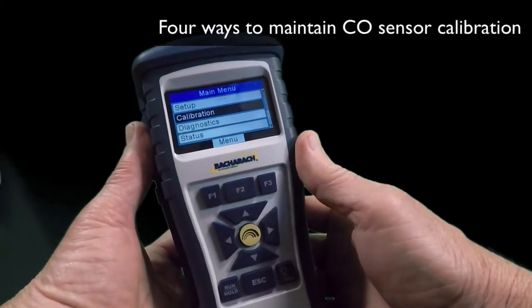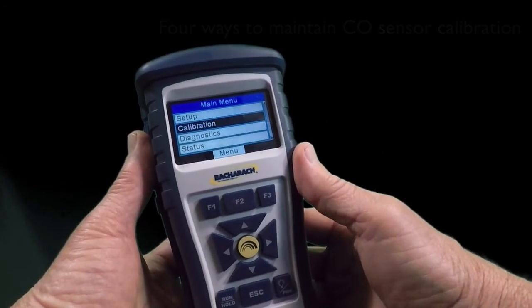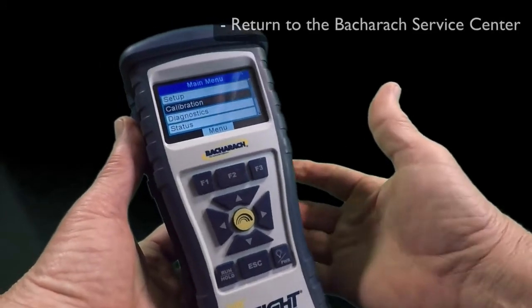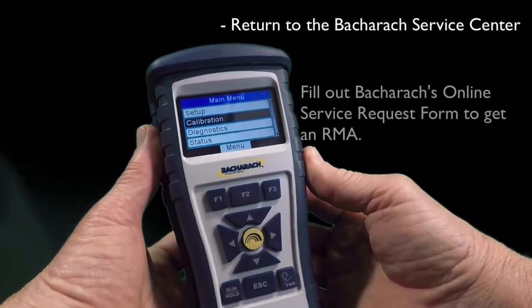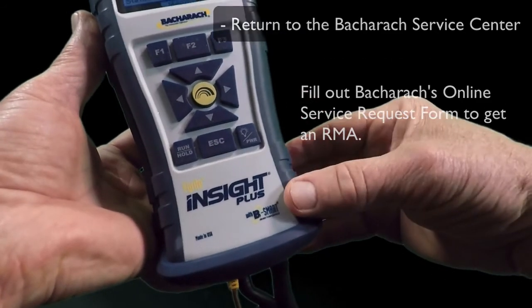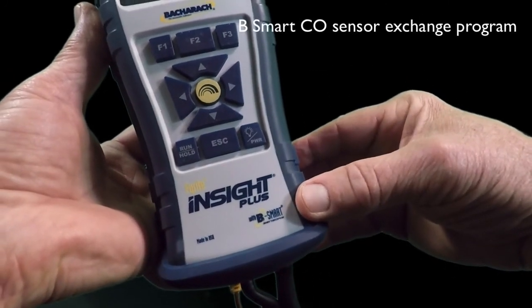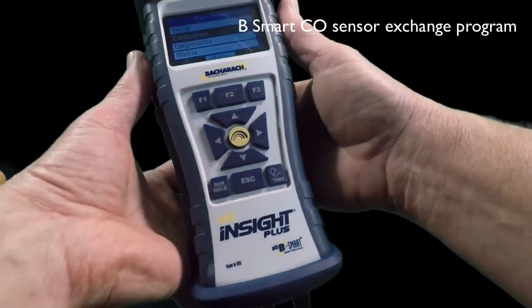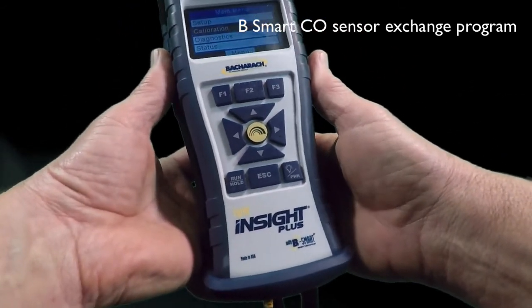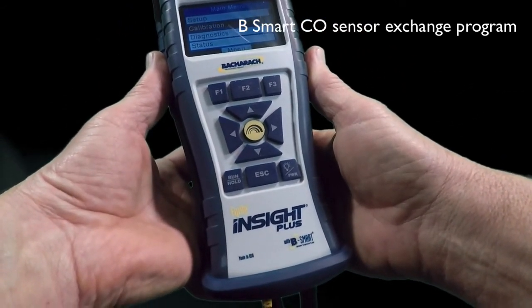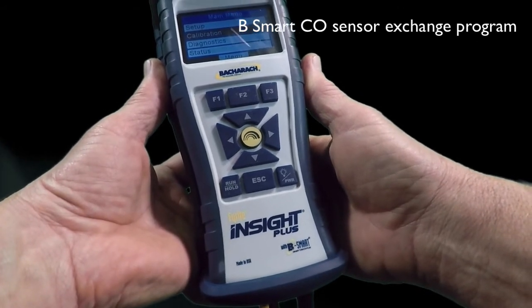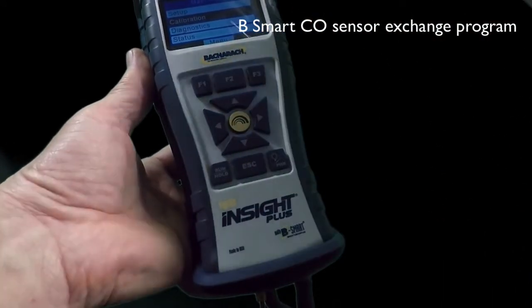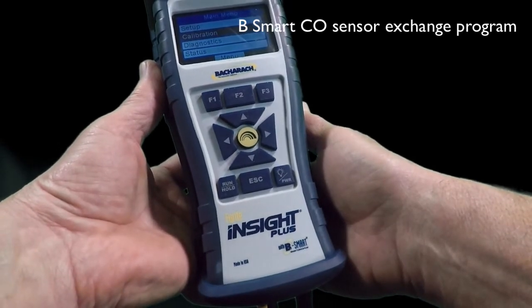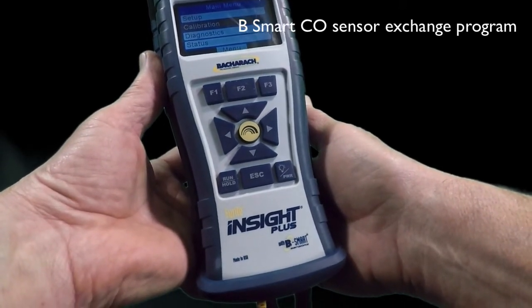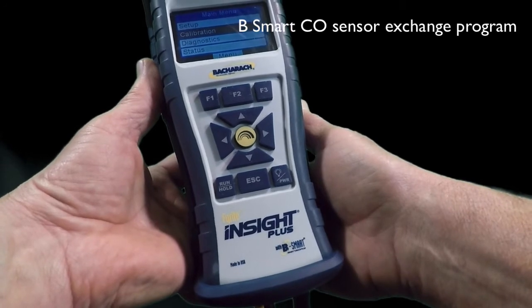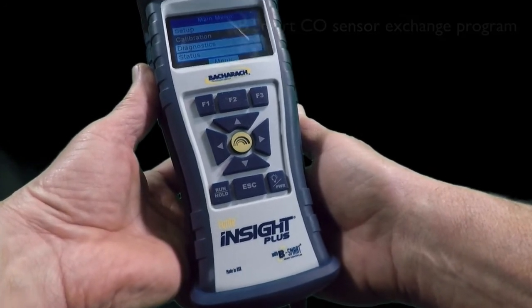Bacharach has come up with 4 options for calibrating, particularly the CO sensors. You can always send the instrument back into Bacharach for service. The second way is to sign up for a B-Smart sensor program. Basically, you'll receive a calibrated carbon monoxide sensor in the mail. You go to the calibration menu, select B-Smart, enter in the code. There'll be a 10-digit numerical code on the side of the sensor. You enter that into the B-Smart screen and return the original sensor to Bacharach in the included addressed stamped envelope.